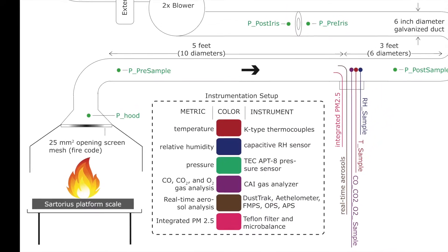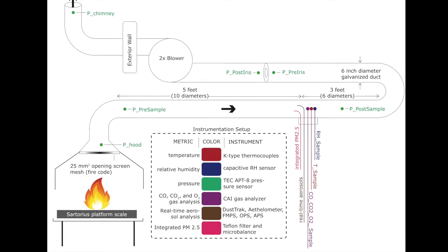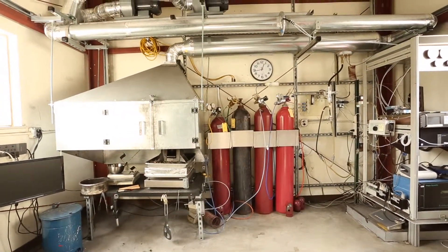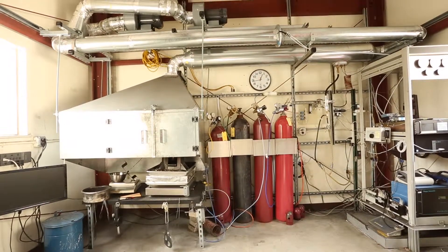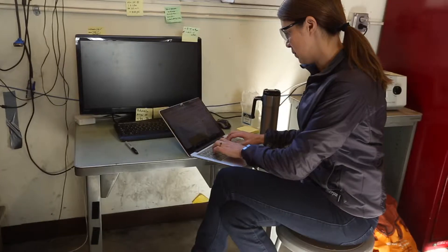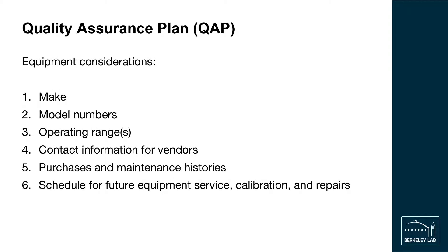When describing the design of your laboratory, include a detailed schematic of the laboratory that contains diagrams of the hood, duct, sampling port, flow monitoring device, and blowers. Any calculations that were performed in the process of designing the laboratory should be written and clearly justified in the quality assurance plan. In fact, any design considerations or calculations described previously in other videos of this training course should be determined for your own testing laboratory and then documented in your quality assurance plan.